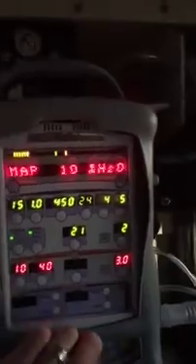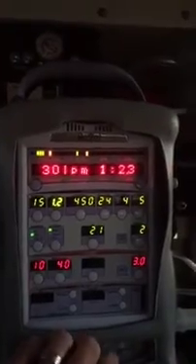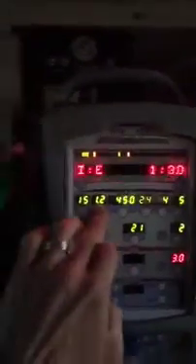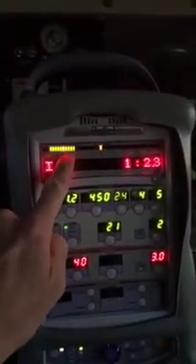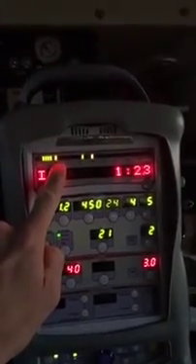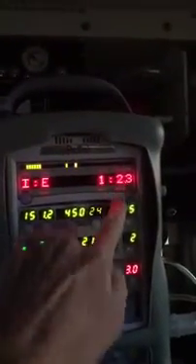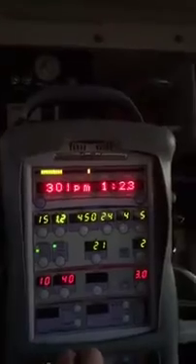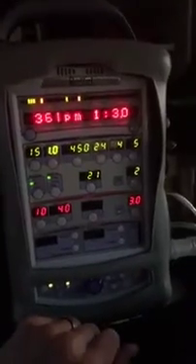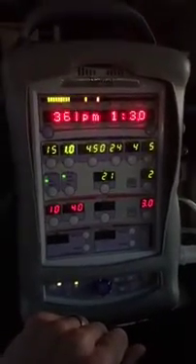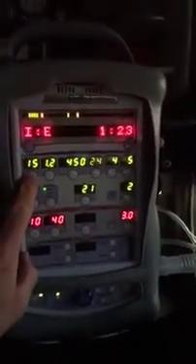So that's how you manipulate that. Now what if I want to shorten the I:E ratio? I can turn my inspiratory time up, and you can see how much longer it takes for the ventilator to deliver that breath — that's a really slow inhalation. You can see what it does to the I:E ratio. That's probably not physiologically comfortable, though there may be some circumstances where it would be beneficial. I've got a super smart respiratory therapist friend who will probably chime in on that.